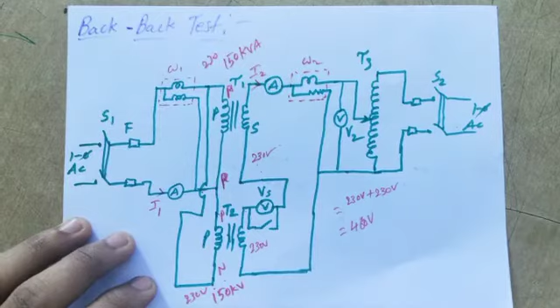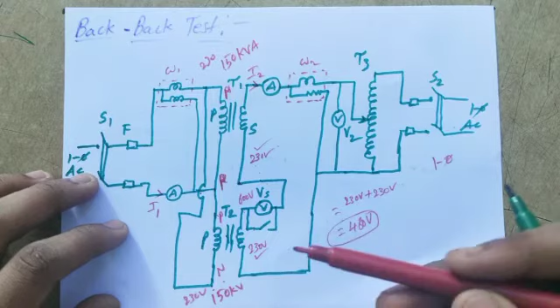So this is single phase supply, but we must maintain at least 460 volts. Why? Because we calculated these are in phase, in the same phase, in an additive manner - this first 230 is adding to the other 230. So when we do the experiment, this should be in phase opposition - in opposite manner. Opposite means 230 minus 230, which equals 0 volts. When the voltmeter shows 0 volts, it means these two transformers are connected in phase opposition.